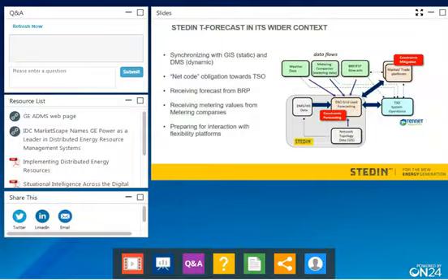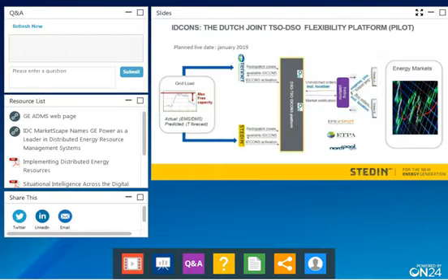That is the last slide I show you here. So you see how the whole setup works. We do the forecast in a forecast application which we developed with GE, and based on the triggers which come out of there, we produce that data to the platform which we run with the TSOs and also DSOs, and we interact with the market. And when we have bids activated in the market to reduce certain loads, the confirmation goes back to the forecast application, so we make sure that we covered a possible congestion point.